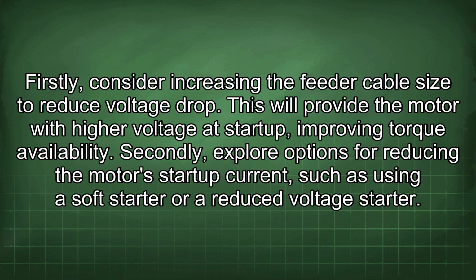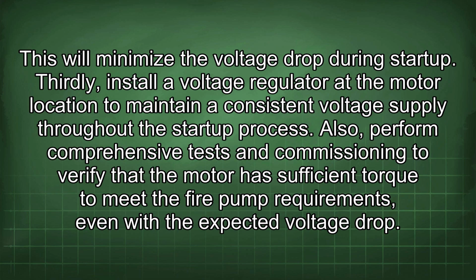Firstly, consider increasing the feeder cable size to reduce voltage drop. This will provide the motor with higher voltage at startup, improving torque availability. Secondly, explore options for reducing the motor's startup current, such as using a soft starter or a reduced voltage starter. This will minimize the voltage drop during startup. Thirdly, install a voltage regulator at the motor location to maintain a consistent voltage supply throughout the startup process. Also, perform comprehensive tests and commissioning to verify that the motor has sufficient torque to meet the fire pump requirements, even with the expected voltage drop.